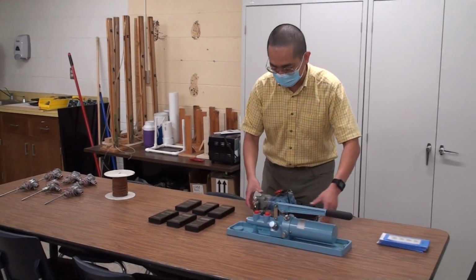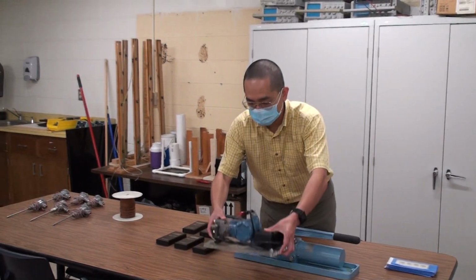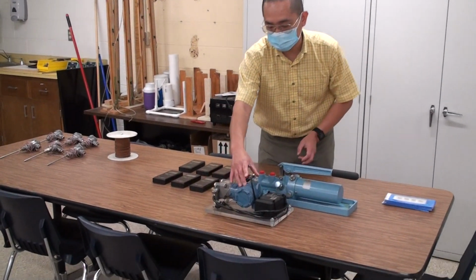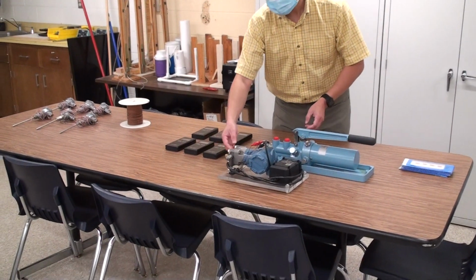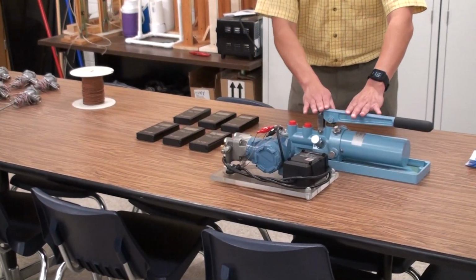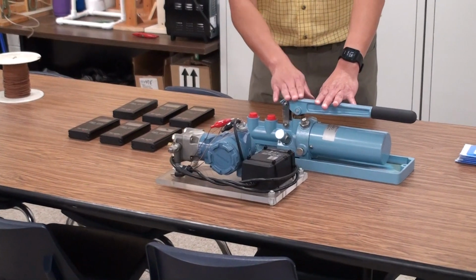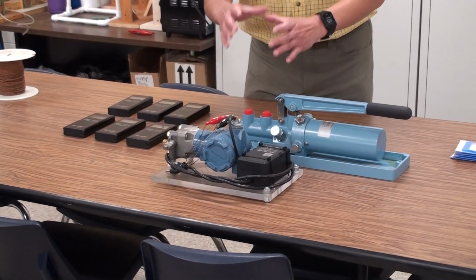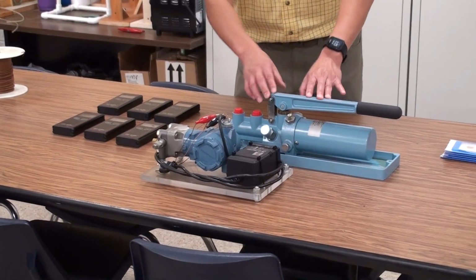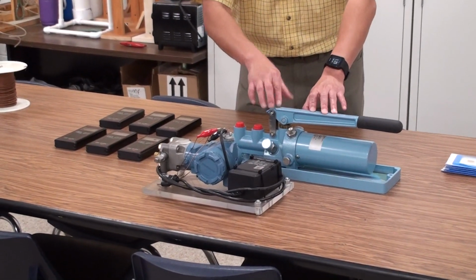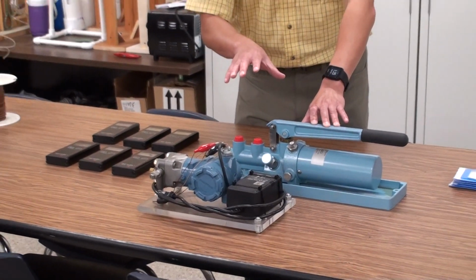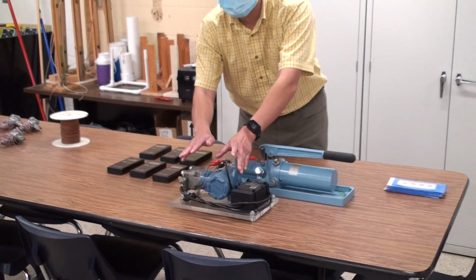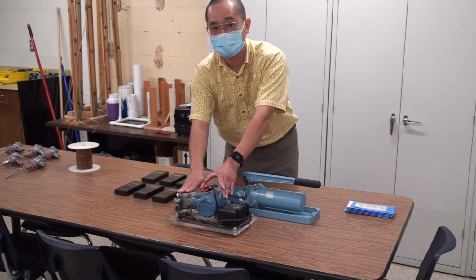We also have a transducer with a diaphragm in it. We pressurize this using a dead weight tester, putting different weights on it with a piston and cylinder, which puts a known pressure on the system.